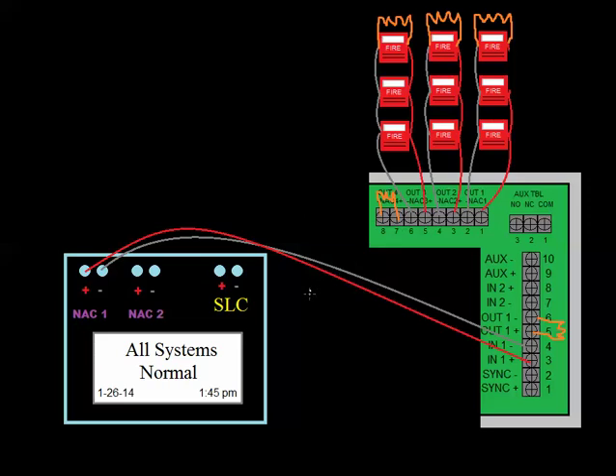Think about how this thing's tripped by using just 24 volts to input 1. Again, depending on dip switch settings. But one feature of these panels is that the auxiliary terminals right here, those have a constant 24 volts DC present at them.